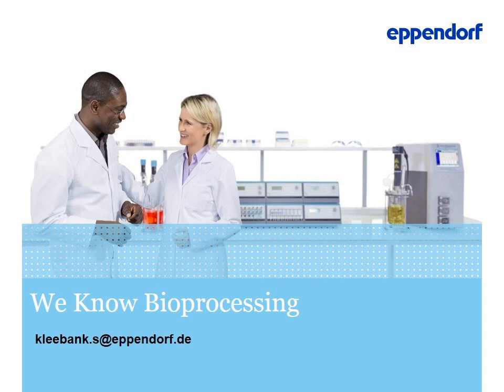And can you describe the method for pO2 and pH measurement? Are there probes included, or do these need to be aseptically installed? Yes, for DO sensors, we have the polarographic sensor that can be put into the DO port, so you don't need to autoclave the sensor. The sensor can stay connected at our control system, so you don't need to wait for polarization. And when the bioreactor is ready, you can simply put the DO sensor in the non-invasive DO port. Regarding the pH sensor, we are using normal glass sensors, so you can separately autoclave them, and then you can mount them into the bioreactor under the laminar flow using a PG 13.5 port of our head plate.